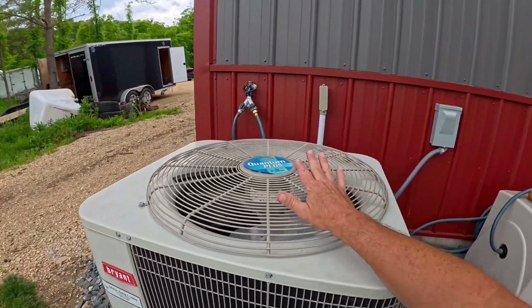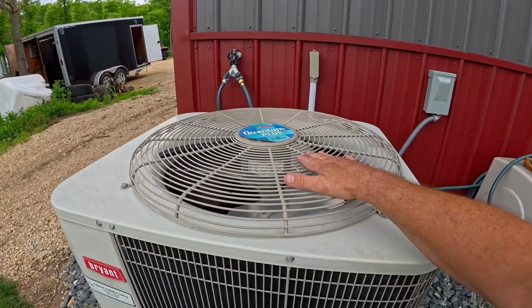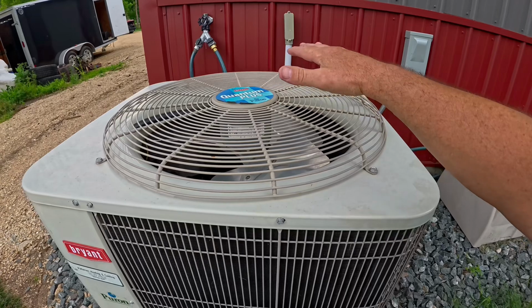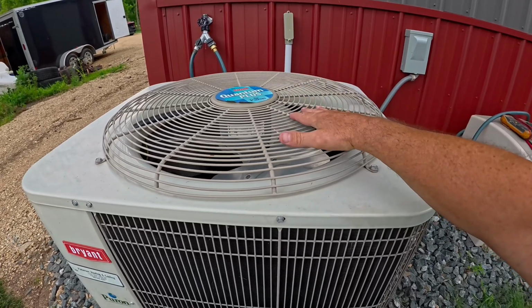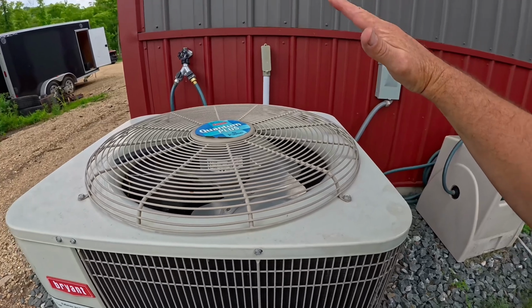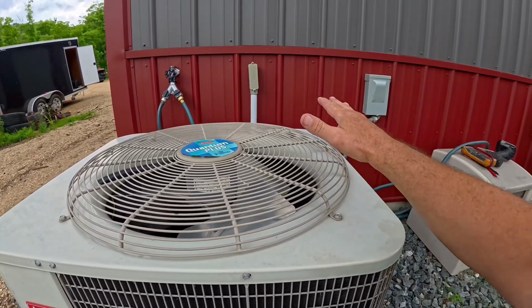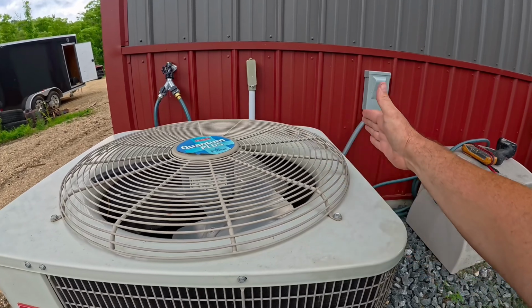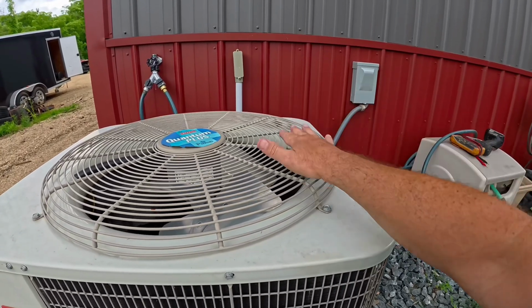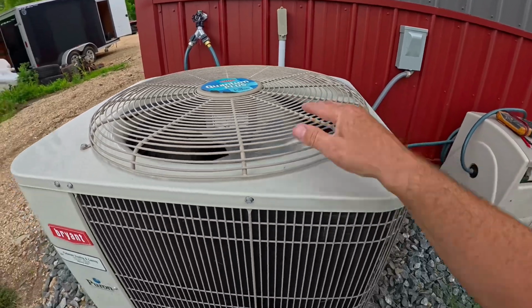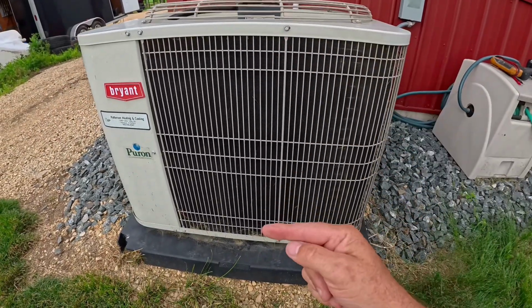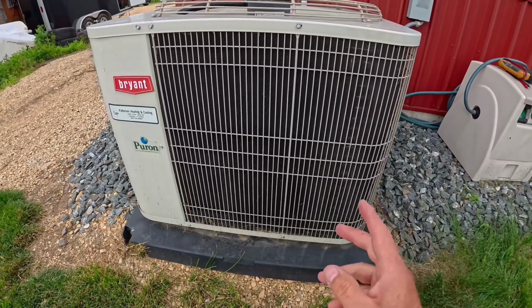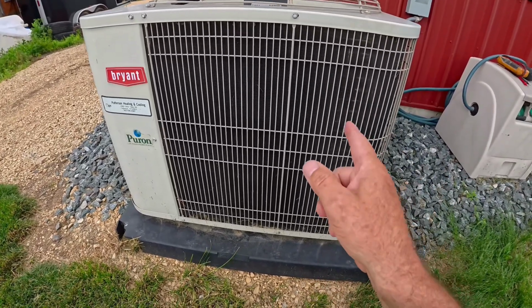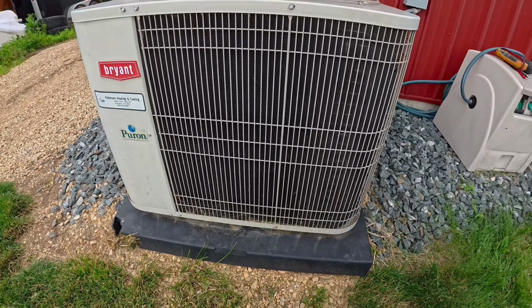Now back to the airflow coming out the top of this unit. Right now it's not running, obviously, so we can talk, but under normal running conditions, the airflow pretty much comes straight up, maybe at a slight angle away from the unit. If you ever experience the air coming out at a 90-degree angle off of the unit and it is extremely hot, that is a sure sign that your coil is plugged and the fan is not able to move air through the coil and remove the heat. Now keep in mind, if we can't remove the heat from the coil, we can't remove the heat from your house. So now let's talk about some basic maintenance and things you can do to keep the system running well.